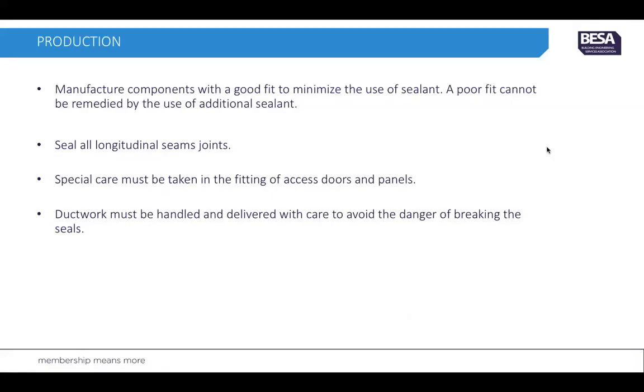The production team must manufacture the components with a good fit to minimize the use of sealant. A poor fit cannot be remedied on site by the use of additional sealant, so it's important to get the manufacturing of the components correct. All longitudinal seam joints must be sealed, and special care must be taken when fitting access doors and panels, because these are very prone to leakage.